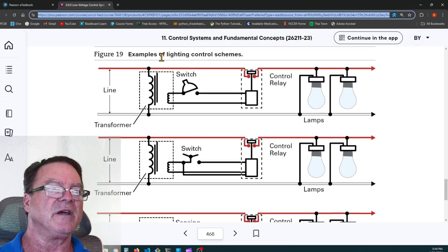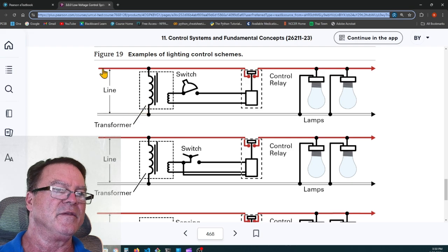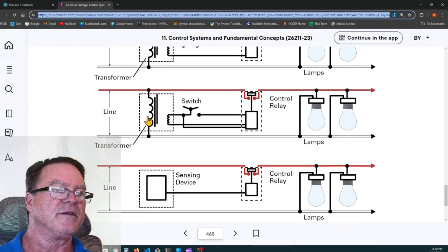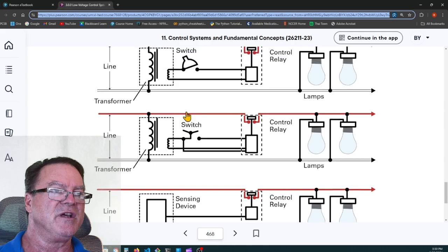So here you're using examples of lighting control systems. Here's the line side. They're using a control transformer to step down the voltage, and then the switch will operate a relay that connects the line voltage to the lights, and it goes back on the neutral. Here, the same thing. They're using a small control transformer to step down the voltage, and you can use a two-position switch that will do the same thing.